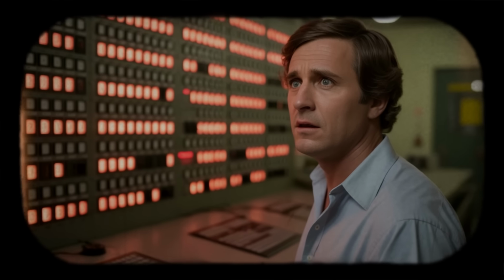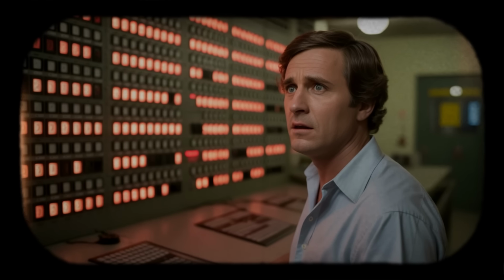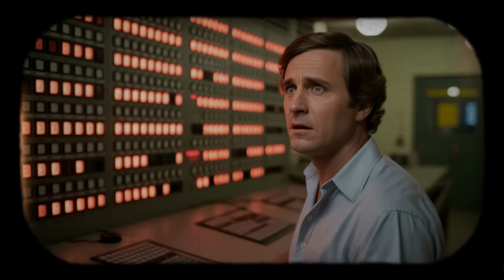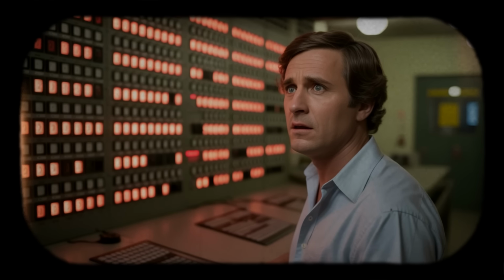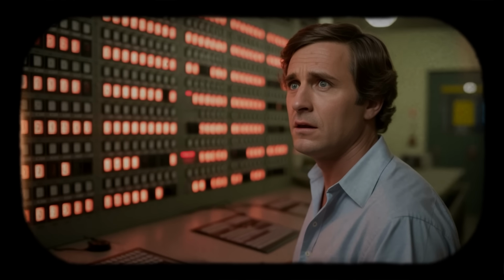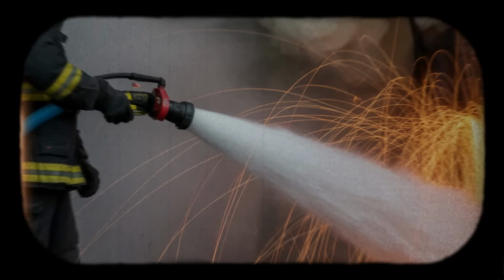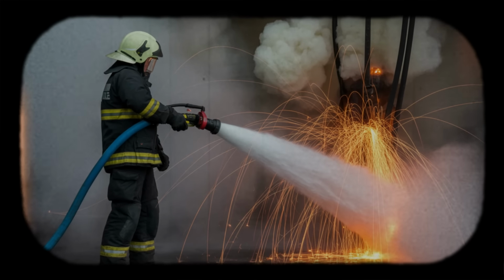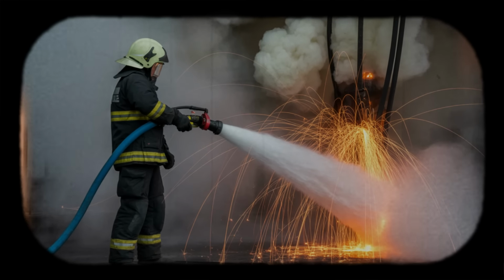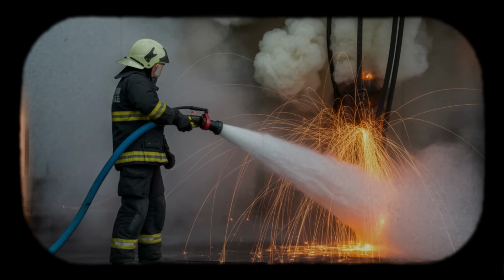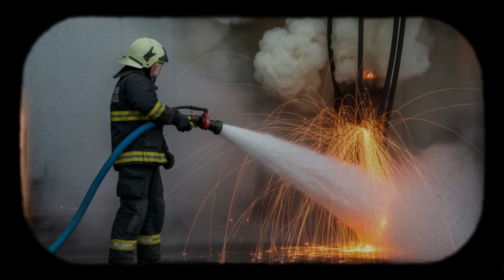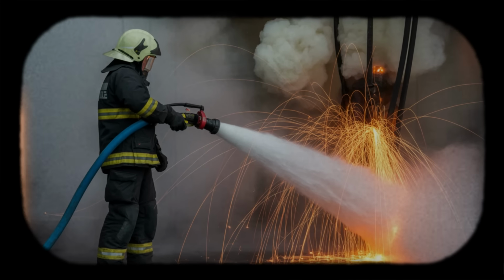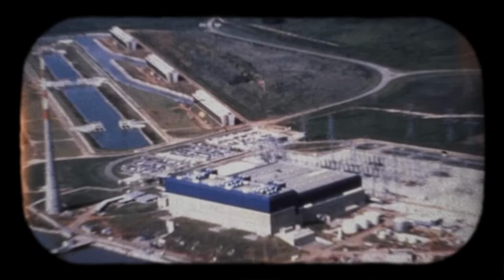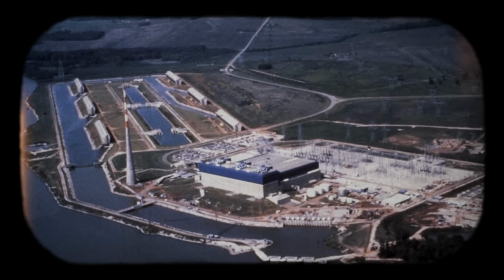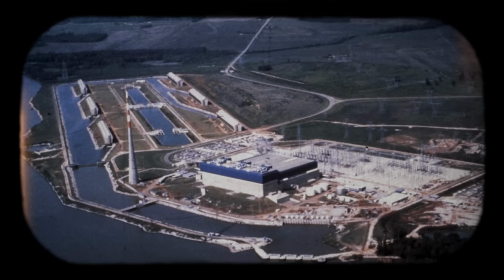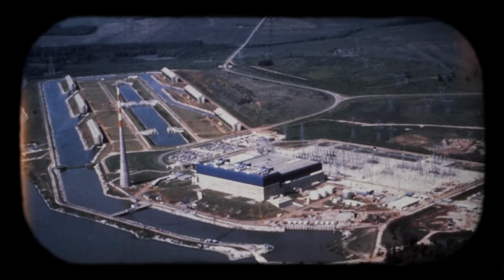When insulation ignites, combustion occurs at the contact points between conductors. Extinguishing agents applied from above or the side have difficulty penetrating to the core of the bundle where fuel and heat concentrate. Carbon dioxide works by reducing oxygen concentration below the level needed to sustain combustion, typically below 15% by volume. In open areas, this is effective. In confined cable bundles, oxygen can remain trapped in small pockets, allowing smoldering to continue even after CO2 application. The fire appears extinguished when surface flames disappear, but internal combustion persists. Minutes after firefighters move on, flames reignite. The preliminary investigating committee noted water fog was eventually necessary despite electrical hazards.